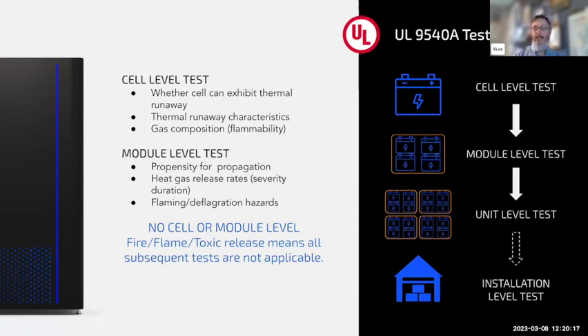UL has a testing protocol known as 9540A. The thing to know is this is not a pass or fail test. So sometimes people say, oh, we passed UL 9540A. That's not true. What happens is UL just runs the batteries through a series of tests, and then we watch and record what happens.